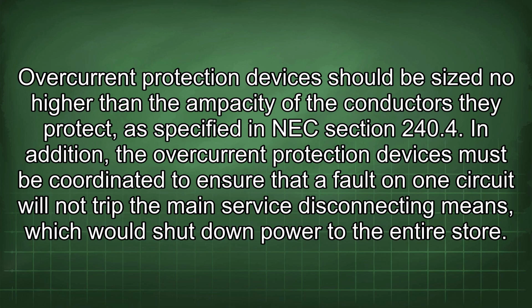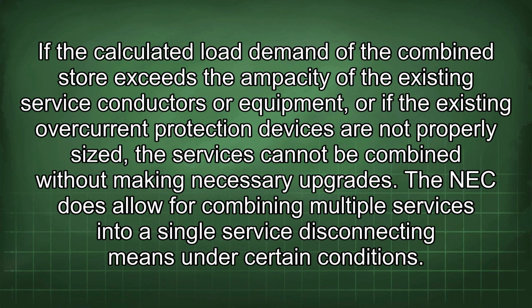NEC Section 240.4. In addition, the overcurrent protection devices must be coordinated to ensure that a fault on one circuit will not trip the main service disconnecting means, which would shut down power to the entire store. If the calculated load demand of the combined store exceeds the ampacity of the existing service conductors or equipment, or if the existing overcurrent protection devices are not properly sized, the services cannot be combined without making necessary upgrades.